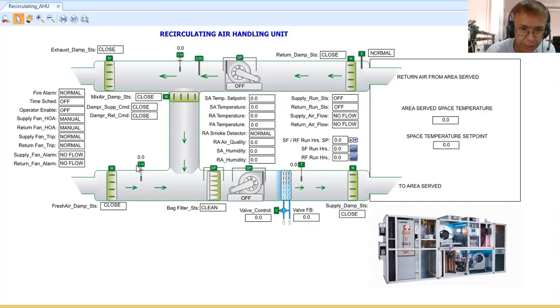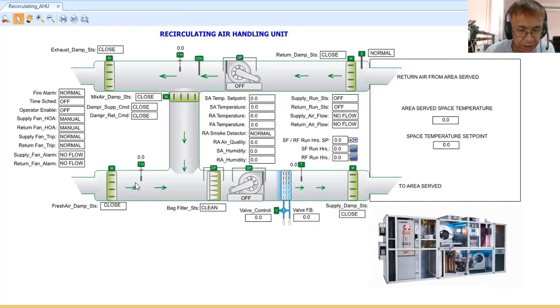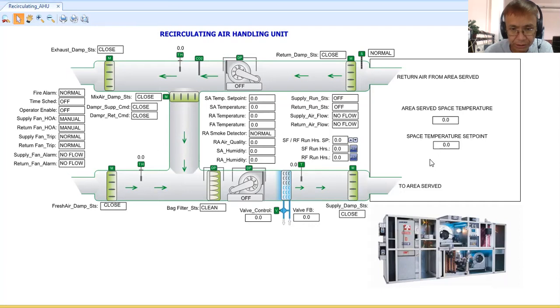Other field devices installed in the air handling unit include temperature sensors. The TH sensor is a combination of temperature and humidity, used to check the ambient condition of the intake air — both temperature and humidity. After the cooling coil, another temperature sensor checks the temperature of the air that will be delivered to the area.